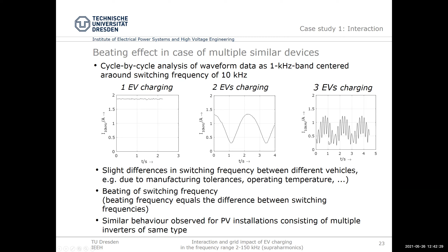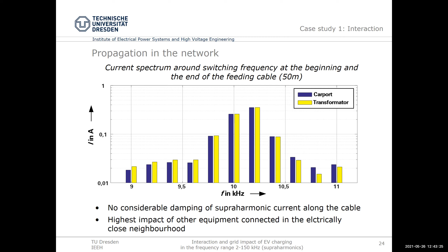Last but not least, for this example, we looked at the propagation in the network. Remember, we did a parallel GPS-synchronized measurement of the current at the beginning and end of the feeding cable. We were curious whether, due to cable capacitance, there might be some damping of the current, but that cannot be confirmed, at least for the 50 meters of cable in this installation. Exactly the same current that we injected at the end reached the bus bar of the transformer. The voltage will be lower for sure, because you have different devices connected which serve as a back path for the emission.